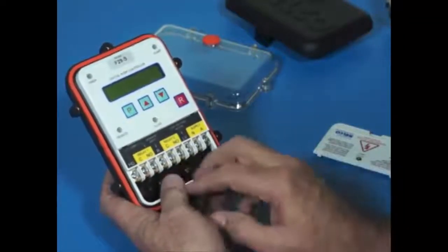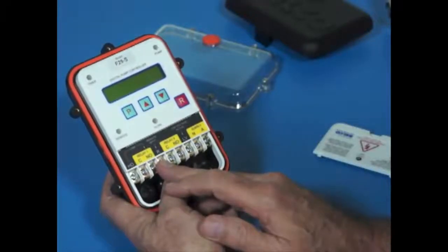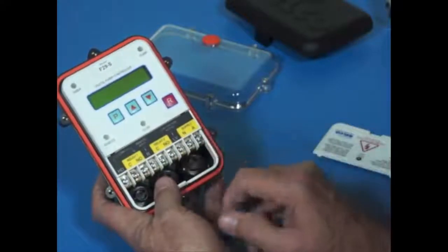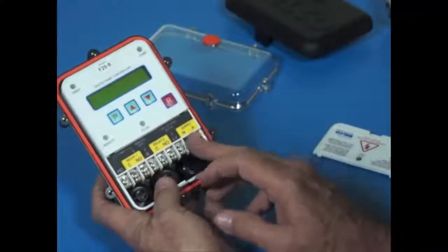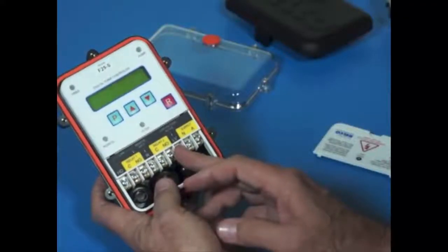The F29 also includes a remote input. You can bring a remote input from a tank level switch or a pressure switch into the F29 using the remote input terminal here, and you can power that external switch through a take-off from the low voltage active terminal. So if you're running the F29 from the mains, 240 volts or 220 volts, you will have 24 volts AC available here at the low voltage active terminal and that can be used to switch a signal back into the remote input terminal.